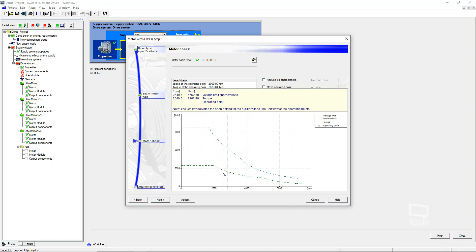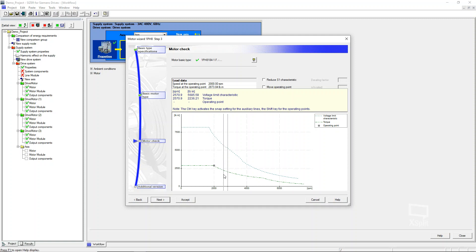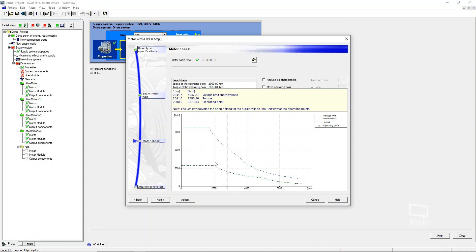So that is significantly less than what the maximum rating is, but not too bad. Probably would do as long as you just understand, you're not going to be able to brake from this higher speed as quick for two reasons. You don't have as much torque and you're going to have more inertia that you're going to have to brake once you're, or more energy that you're going to have to stop. So you kind of just need to understand if you're overspeeding a motor like this, that that's what's going on.